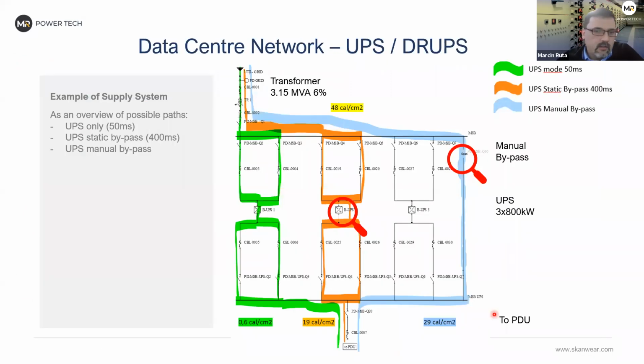I will show you on the single line. That's easier to see. What you can see is the UPS mode, where we expect 0.6 calories. Let's say we can skip this one, there's nothing to improve. We have the UPS with static bypass, just on the UPS internally, and then we start to see 19 calories. I'll explain why. And then we have a manual bypass with 29. So our biggest concern are those 2 scenarios.